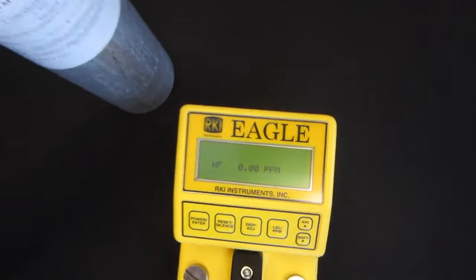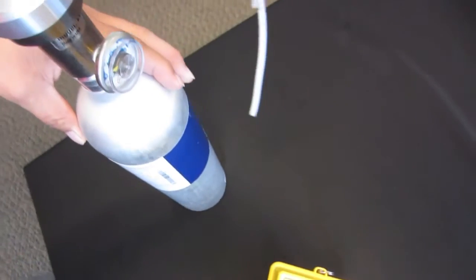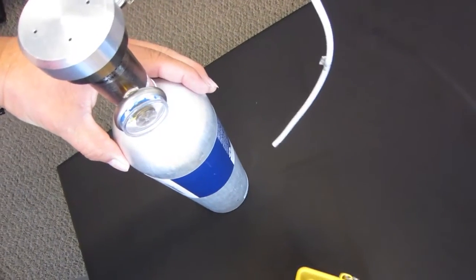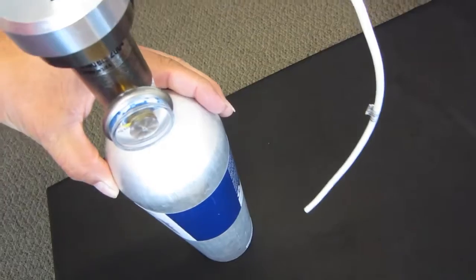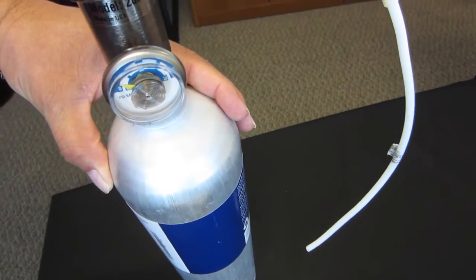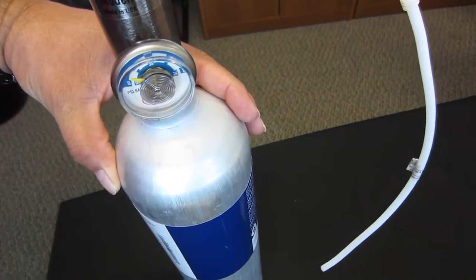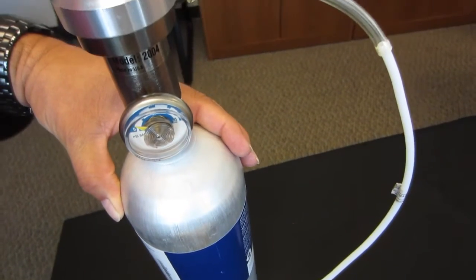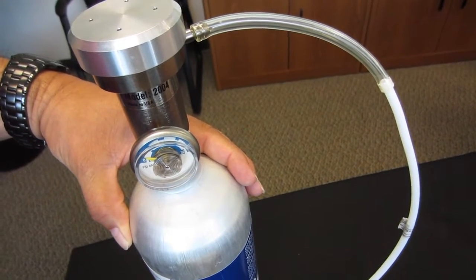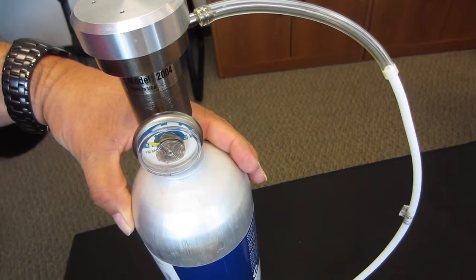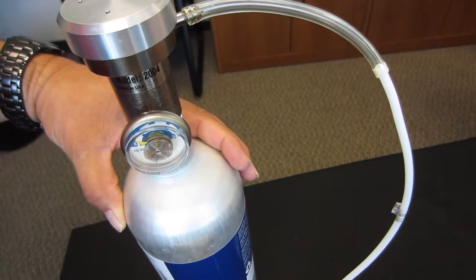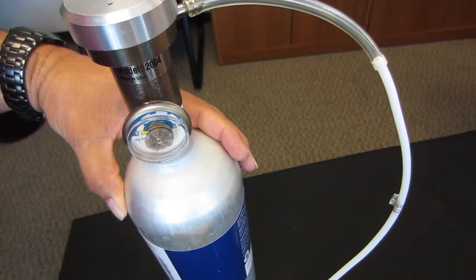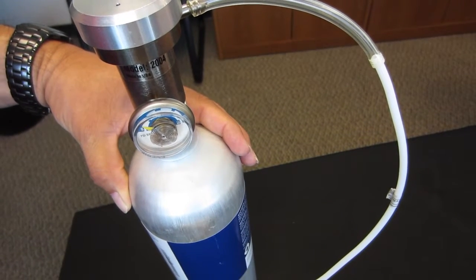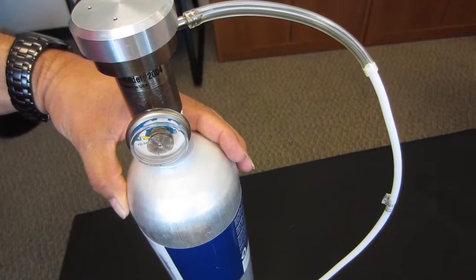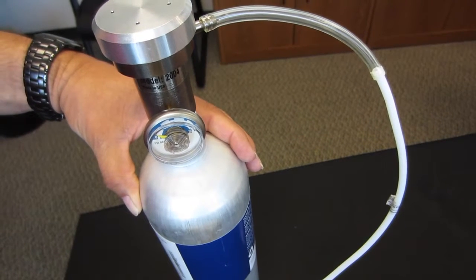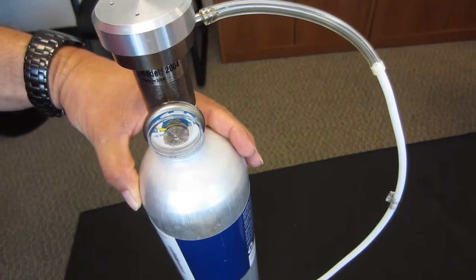Okay, right now we've got the regulator attached, this demand flow regulator attached to the cylinder. This demand flow regulator is normally off when it's not connected to a vacuum suction being applied by a pump. So basically it's off right now, but as soon as I connect it to the Eagle's pump, it's going to open up the valve in the regulator, and the gas will start flowing automatically. The opposite of that is when you're done bumping or calibrating, just simply pull the tubing away from the Eagle and the regulator automatically turns off.